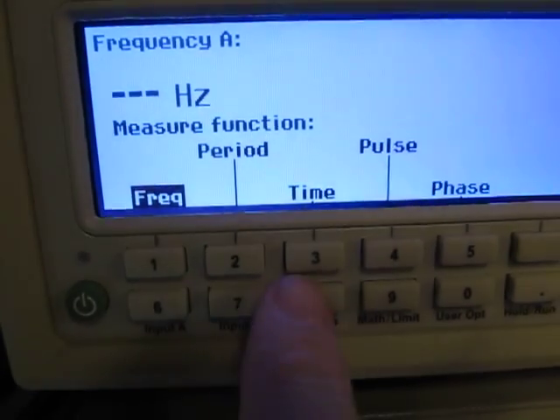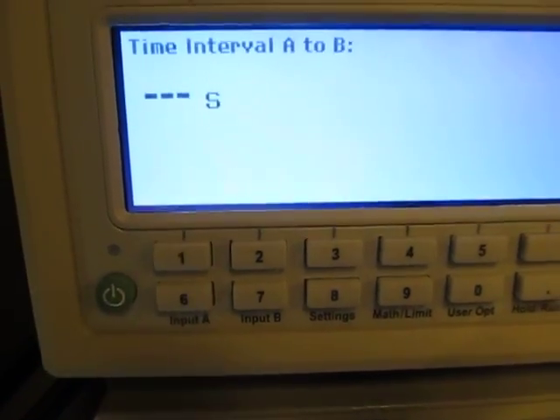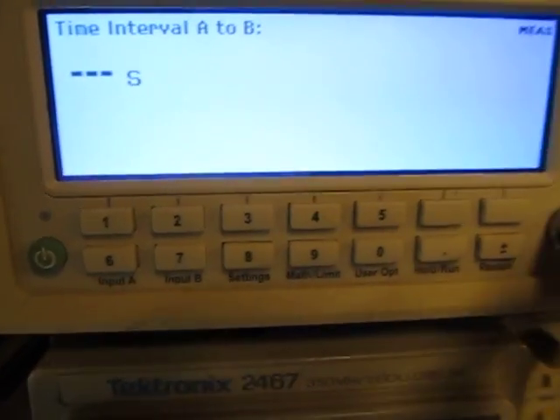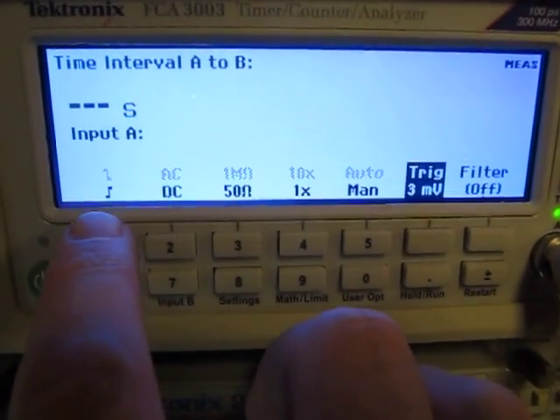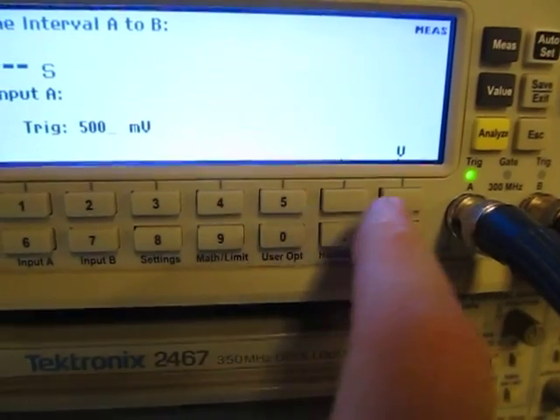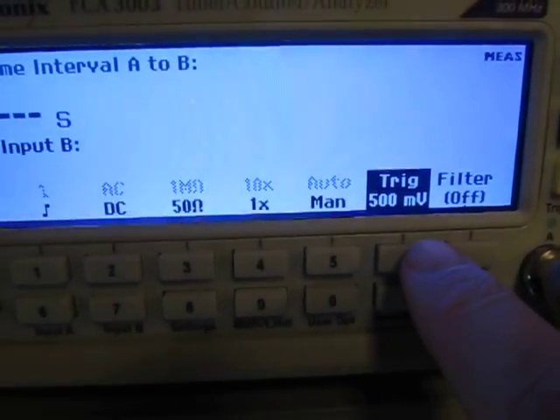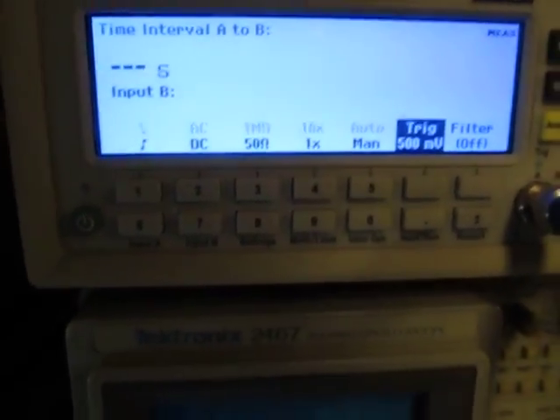Now we'll take those signals and bring them into the counter — one on channel A and the other on channel B. I'll hit Measure, select a time interval measurement from A to B. I'll also make sure the channels are set up correctly: the pulses go from 0 to 1 volt, so input channel A is set to rising edge, DC coupled, 50 ohms, no attenuation, with a manual trigger and trigger level at 500 millivolts. Channel B is configured the same way.